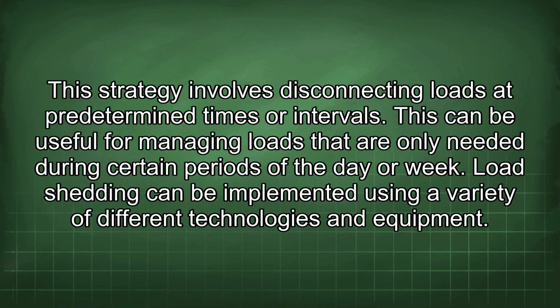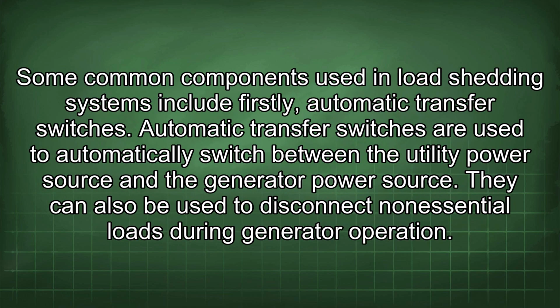Load shedding can be implemented using a variety of different technologies and equipment. Some common components used in load shedding systems include firstly, automatic transfer switches. Automatic transfer switches are used to automatically switch between the utility power source and the generator power source. They can also be used to disconnect non-essential loads during generator operation.